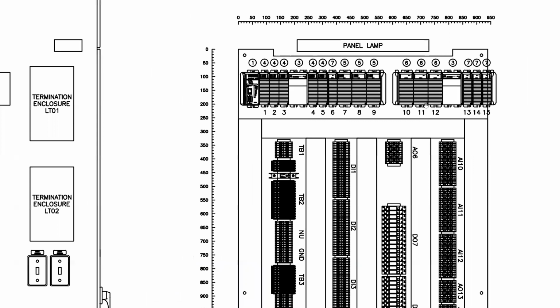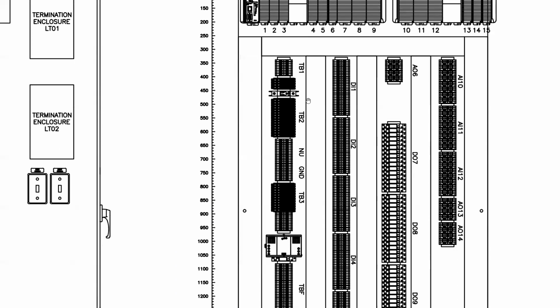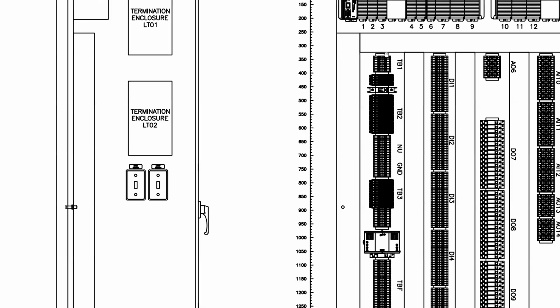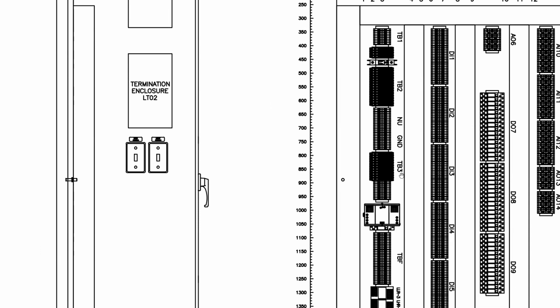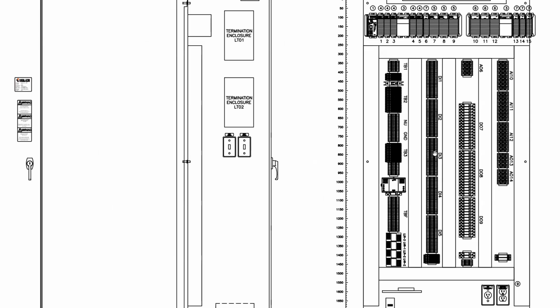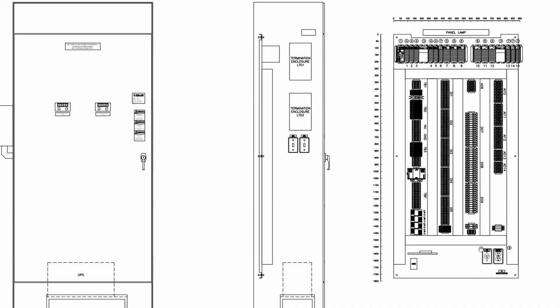Panel layout, preferably to scale. So you've got your processor at the top. You've got all your different terminal blocks. These are labeled TB1, TB2, TB3, DI1, DI2, DI3. So that would be your power. Probably, I don't remember this panel, but probably 120 volt. And then 120 volt non-UPS, then UPS power. That looks like a 24 volt power supply. These will be your digital input terminals, your digital output relays, and your analog input and then analog output relay. Analog input and analog outputs. So these are all labeled receptacles.